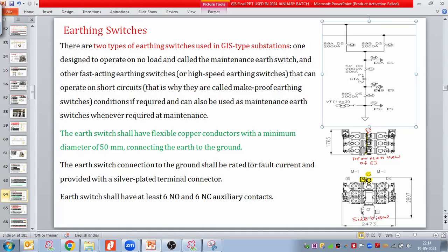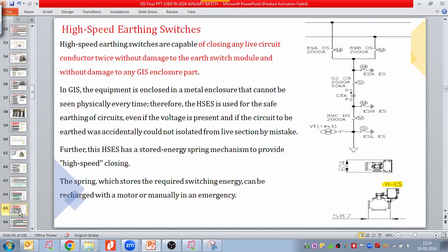This one is the maintenance earthing switch, which is motor operated, and this is the high speed earthing switch, which is spring charged operated. So due to the spring operation, this is fast compared to the motor operated. The earthing switch shall have flexible copper conductors with a minimum diameter of 50 millimeter, connecting the earth switch to the ground. Earth switch connections to the ground shall be rated for fault current and provided with a silver plated terminal connector as well. The earthing switch we take generally 6 NO 6 NC normally auxiliary contacts.